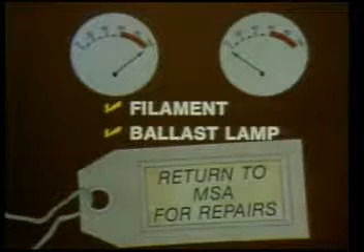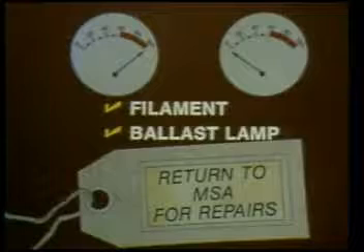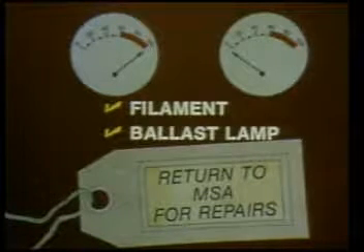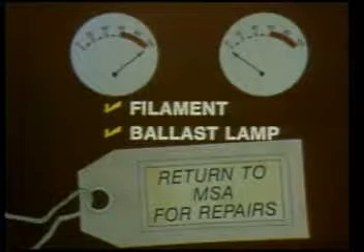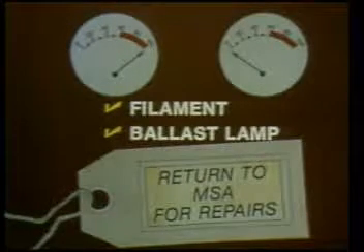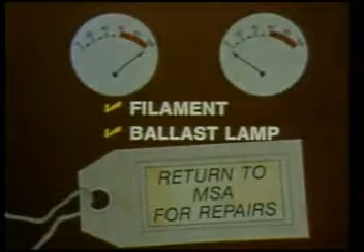Finally, if the meter needle remains either upscale or downscale, and replacement of the filament or ballast lamp fails to correct the situation, one of the other arms of the Wheatstone bridge has failed. If this happens, the instrument must be replaced or returned to MSA for repairs.